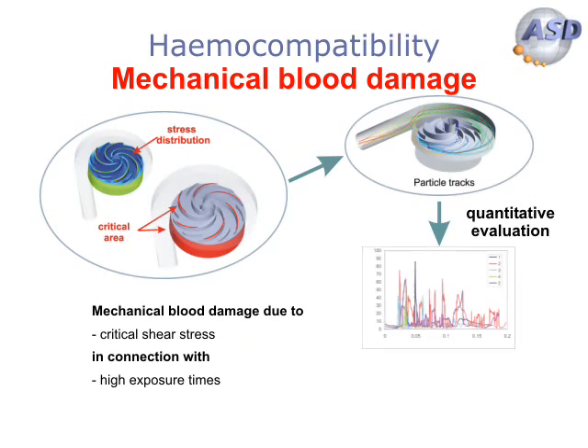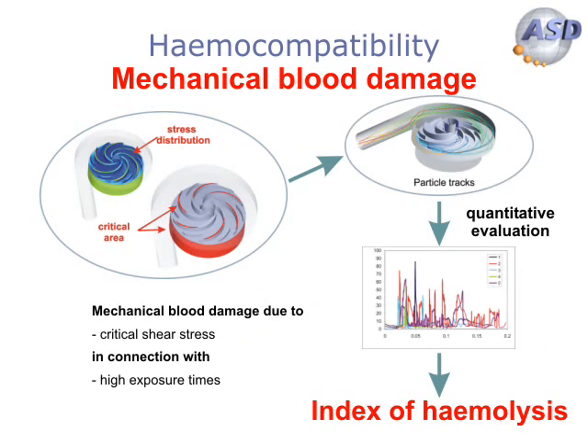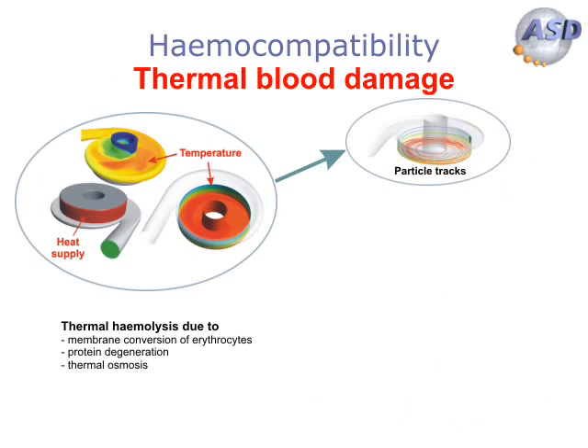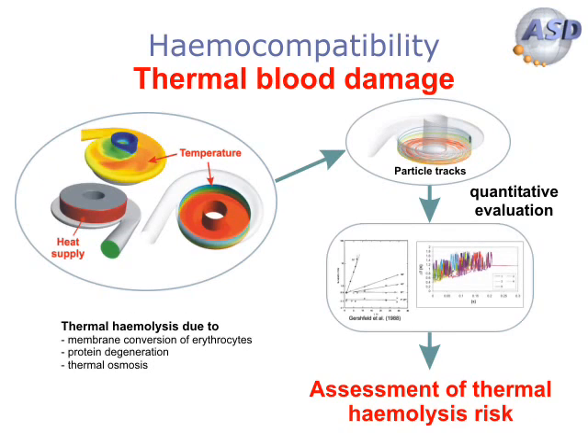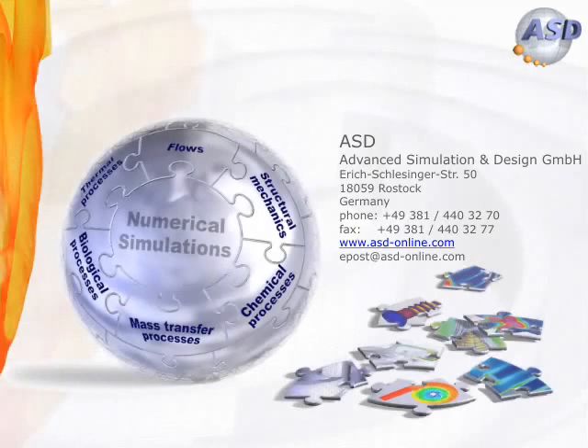Another critical design parameter is to avoid hemolysis due to high mechanical loads on the blood cells. ASD has a pioneering role in the development and implementation of numerical prediction tools regarding hemolysis and other aspects of hemo-compatibility for an efficient optimization of blood pumps.